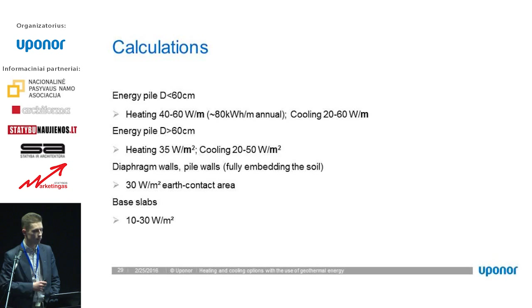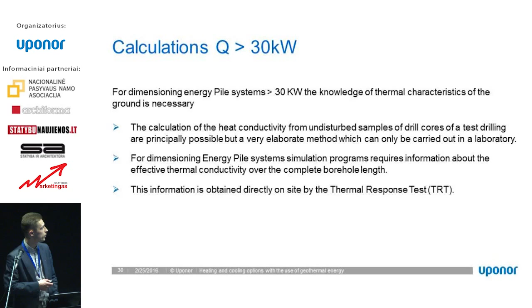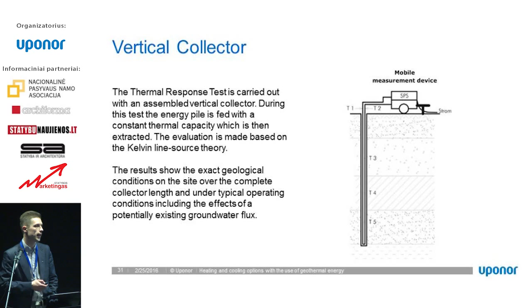If the load is quite high, higher than 30 kilowatts, you need to know the soil's heat conductivity, and the best way is to perform a thermal response test. That means special equipment is used to circulate heated water - we put pipes in the ground, circulate heated water, and see how much energy dissipates, how the ground's heat conductivity is, and how much energy we can get from it. This is the best way to assess how much we can get from the ground.